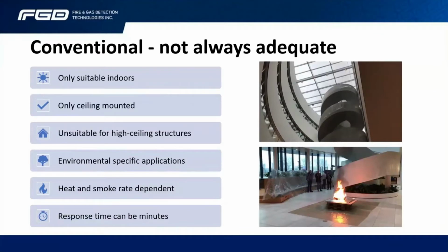They tend to only be ceiling mounted, and that can mean that they're not so suitable for very high structures, because what you have with a fire is the smoke particulates or the heat have to transfer or travel all the way to the detector itself. So you actually have quite a long transit time.